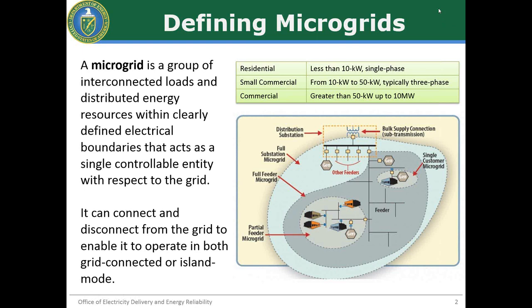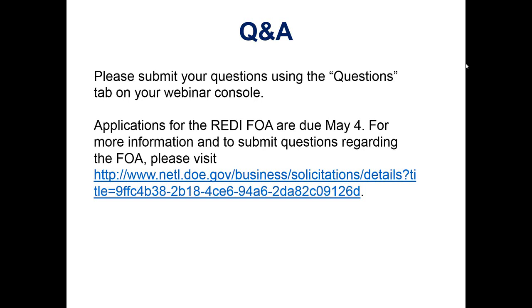Flow batteries. Can they simultaneously perform energy and power functions and benefits, for example, site cost savings and also ancillary regulation for the local utility at the same time? Yeah, there are at least half a dozen functions that a flow battery can perform. Flow batteries can respond as well as, say, lithium-ion batteries to short-term fluctuations, and they can serve as backup and so on. The interesting thing, of course, is you need to develop a careful algorithm which will allow these functions to be active side by side.